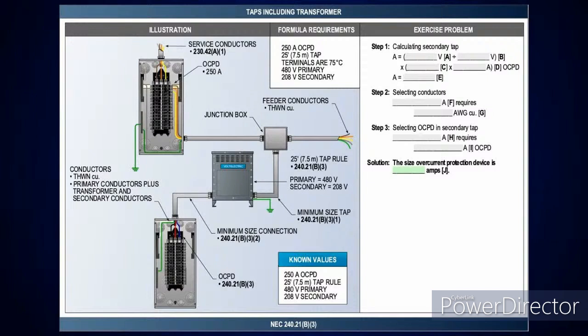Okay? Yeah, and that's one thing I want the students to know: your overcurrent device can exceed your conductor. Sure can, but there's certain cases where it can't. So we want you to know the different areas where, in this case, the load is what you're protecting, and in this case, you're protecting the conductor. If that conductor is at a certain ampacity, you can't exceed that. Sure. And just remember, that is the minimum. I can still go up on my tap size if I want to. That's just a minimum, and then you could go up and have it match something, have the extra amperage there.